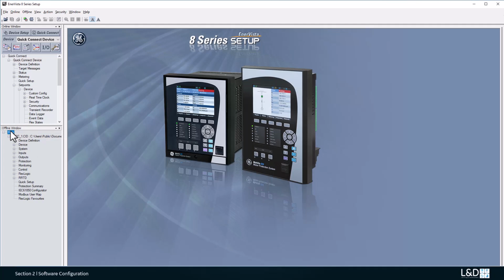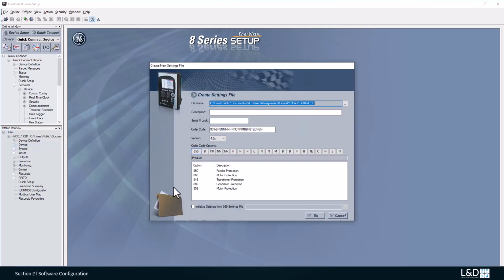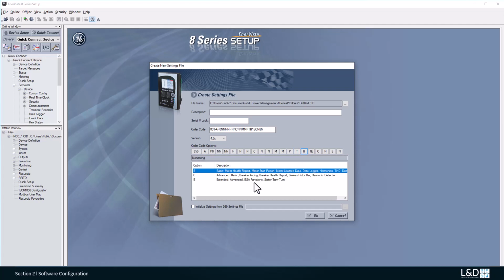The user can create an offline setting file from scratch in the offline window just by right-clicking the mouse and choosing New Setting File. And from here, we can choose the 859 motor relays, and then you can choose different order codes. You can choose the basic or the advanced. So here, if I choose advanced, each option just gives you different functions to choose. And for this, mostly just one option, it's a simplified one. And here you can choose the advanced features. And for the comms, you can choose 61850, advanced cybersecurity, and then click yes, and you can also give this a name.